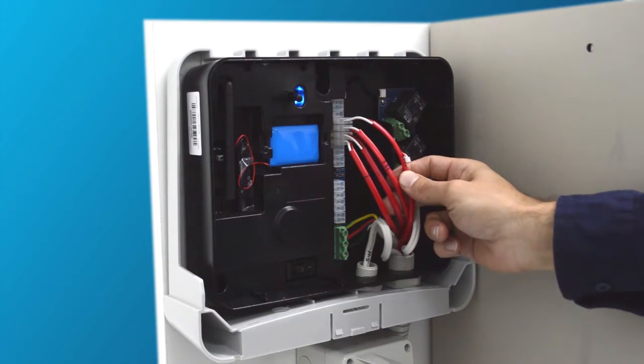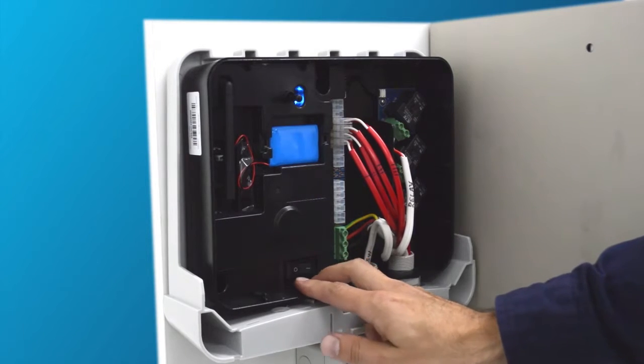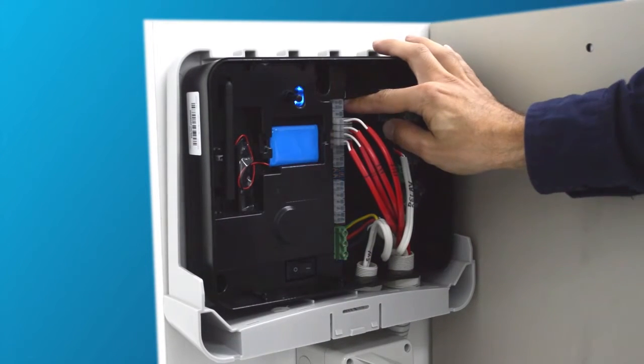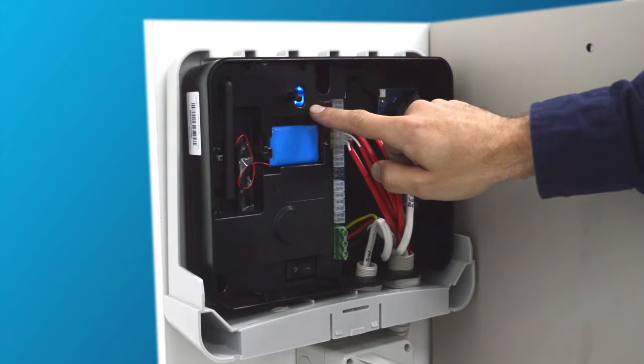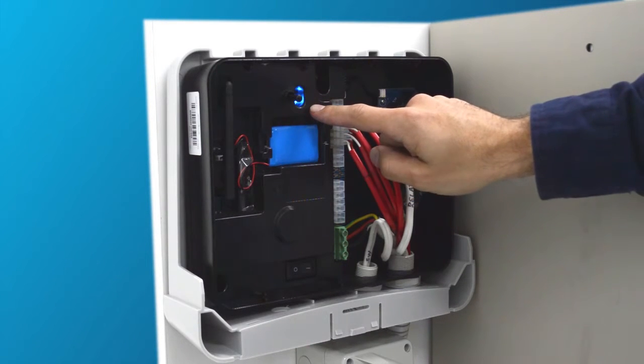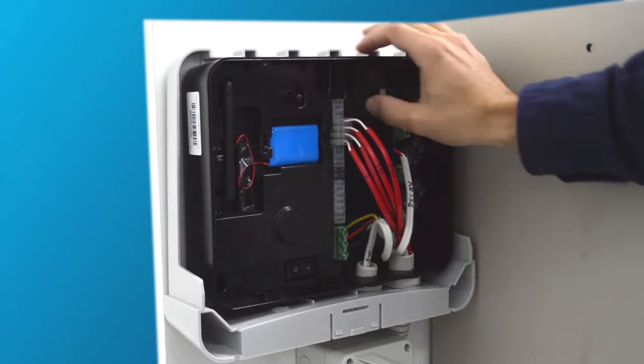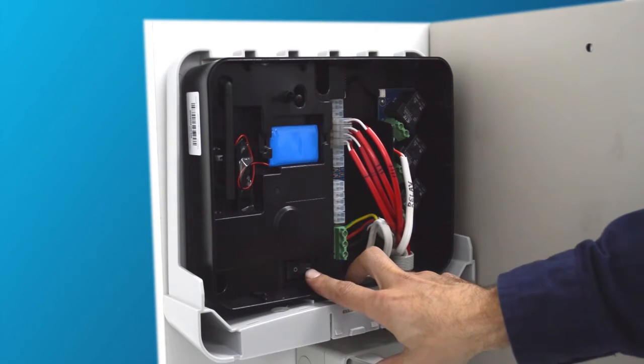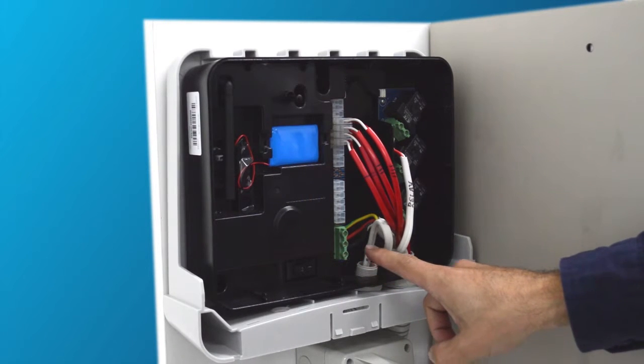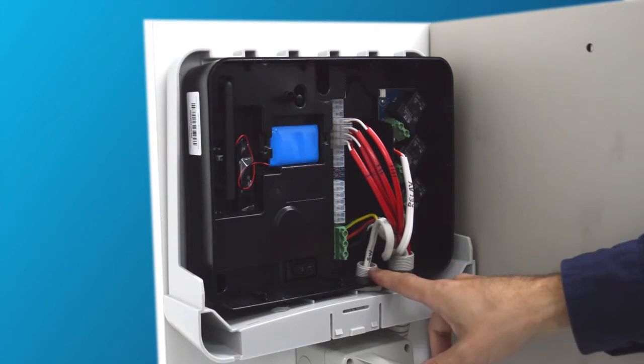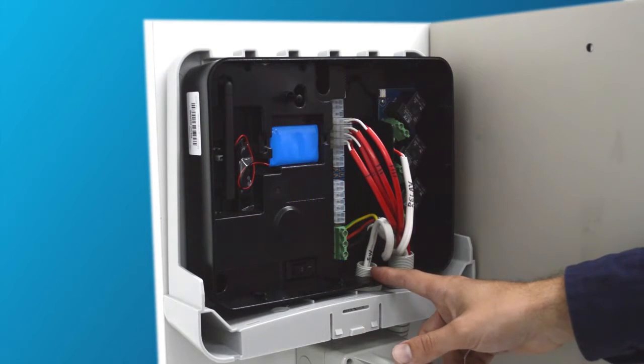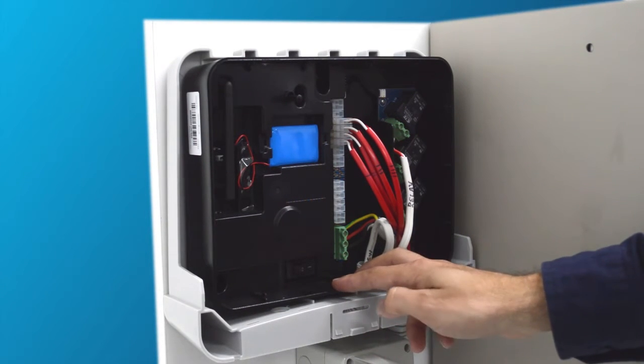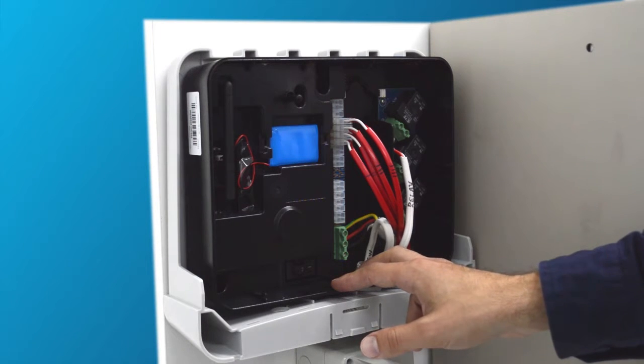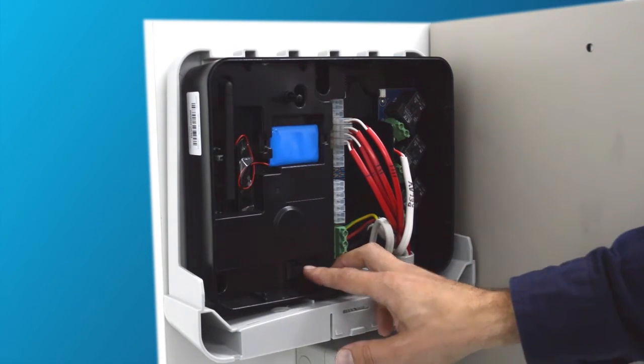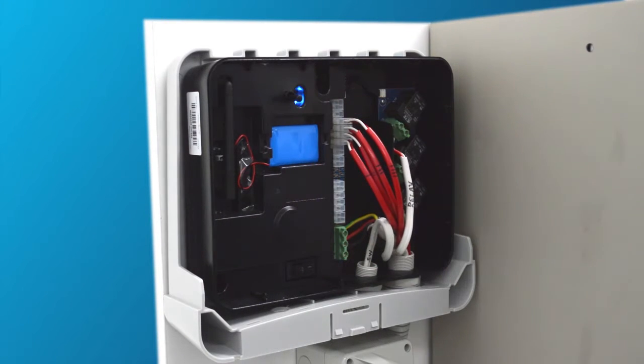With the unit's main switch in the off position, turn the battery switch into the on position. The light at the side of the unit should come on. Now you can turn off the battery switch and turn on the main switch. Using a multimeter, test for 240 volts across active and neutral at the main terminal. As this is a test unit and there's no power active, I cannot display the 240 volts. After you have registered 240 volts at the main terminal, you can turn back on the battery switch and leave it in the on position. You are now ready to test and commission the unit.